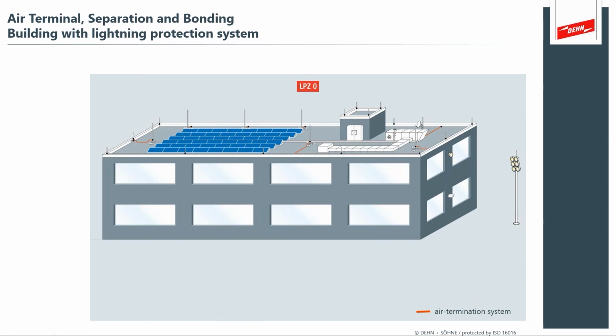So this is one of the points we make, that when you install a lightning protection system for external lightning protection, you have to pay attention to all the aspects: the down conductors, the air terminals, but also the bonding and the separation from the lightning protection system.